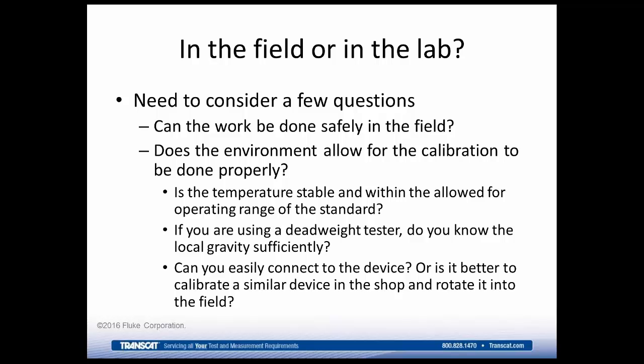And can you easily connect to the device under test? Is it a situation where you're going to have to run 1,000 feet of hose up to the device under test in order to apply pressure to it? Well, that's 1,000 feet of head height offset. Or is it a situation where it's better to calibrate a similar device? So if it's a pressure transmitter, we've got two of them that are very similar to each other, or that's the same model and range and everything. Calibrate one in the shop, rotate it into the field, bring the other one back for calibration. These things need to be considered when making that choice.